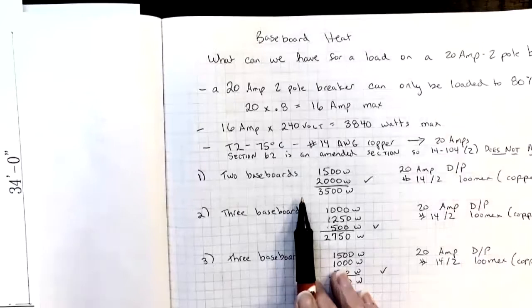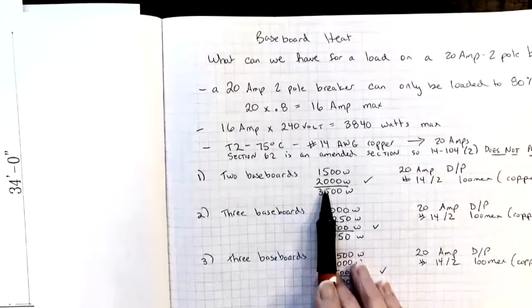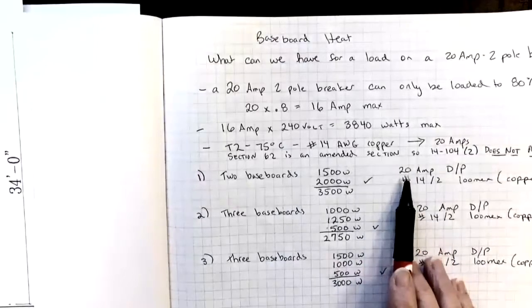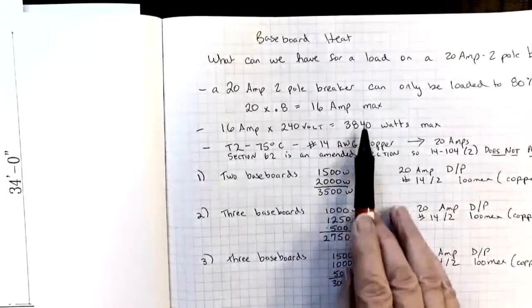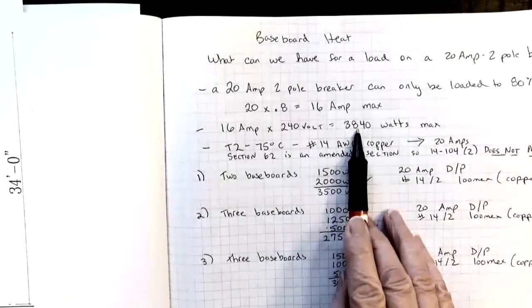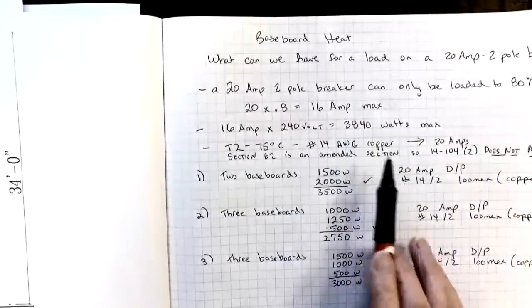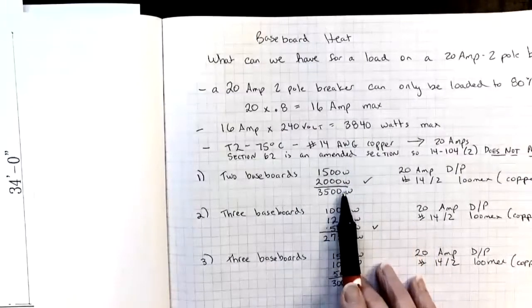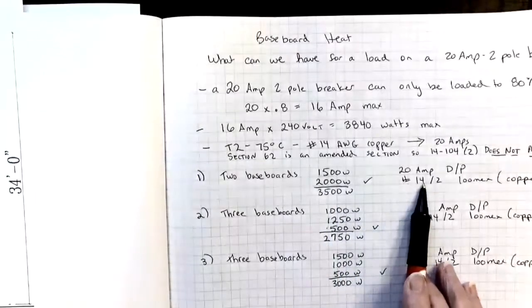Now in the two bedroom house, I had two baseboards in the living room, a 1500 watt and a 2000 watt. So using the rules that we just looked at, when I take 3500 watts and look at it, it fits within our maximum for a 20 amp breaker. So I can use the 20 amp breaker. Also from table two, the wire is good for 20 amps. And so when I divide this out, I end up with less than 20 amps. And so the 14-2 Loomex is fine.